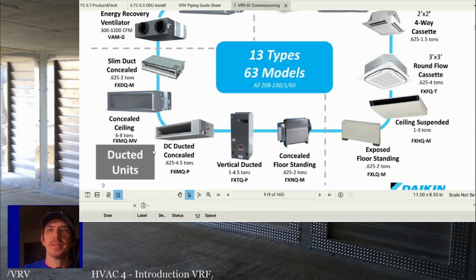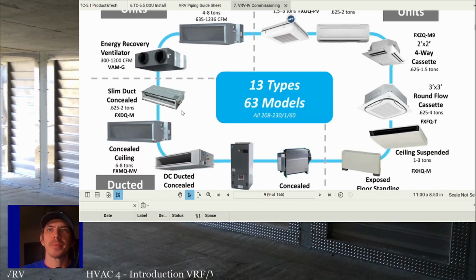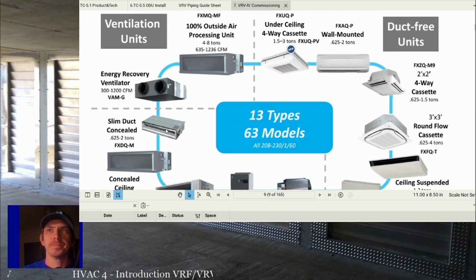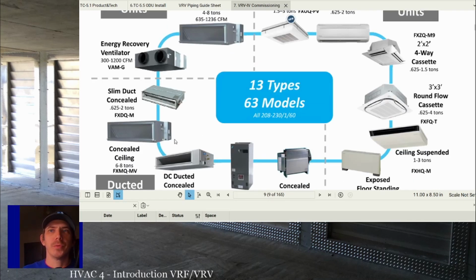Ducted concealed units, all right. The ducted concealed units, something to keep in mind with all of these, is all of these are pretty low static units. So you need to be very careful with these. These units cannot handle a lot of duct work, but they're just basically horizontal air handlers that hang in the ceiling, and then you can duct off of them. But it's generally a very small amount of duct. You need to be very careful making ductwork changes when installing these units because you can run into trouble real fast where you exceed the available static pressure of them.